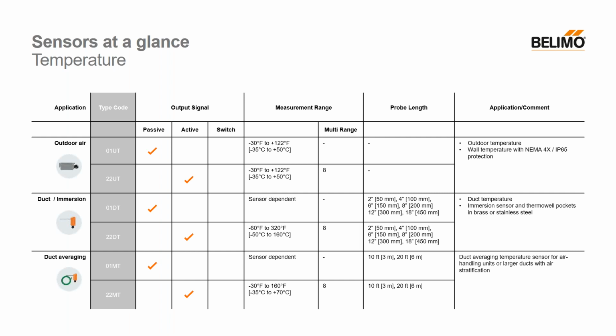Something I want to point out when we look at the sensor offering is that the nomenclature is a little different. If you're just becoming familiar with our sensor product range, 01 at the beginning of any part number is going to indicate a passive sensor, like an NTC or a platinum or a nickel sensor, while a 22 at the beginning is going to be an active sensor with a voltage DC or milliamp output. So again, we offer outdoor air temperature sensors in both active and passive. We offer immersion and duct sensors in active and passive.